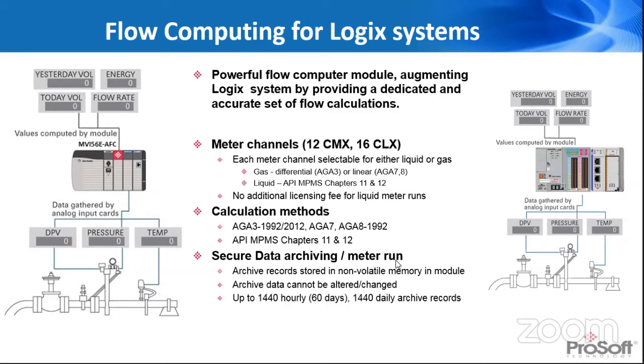When we talk about archiving, that's one of the main things for standalone flow computers. They have to have not only a secure archive trail, but they have to be able to archive at least 35 days of hourly records. And we're able to support up to 60 days, or 1,440 hourly records. That information is all stored in non-volatile memory directly in the module itself.